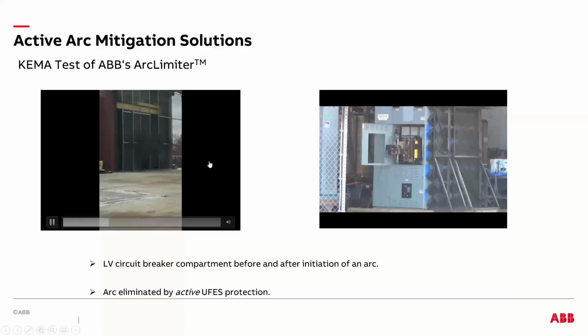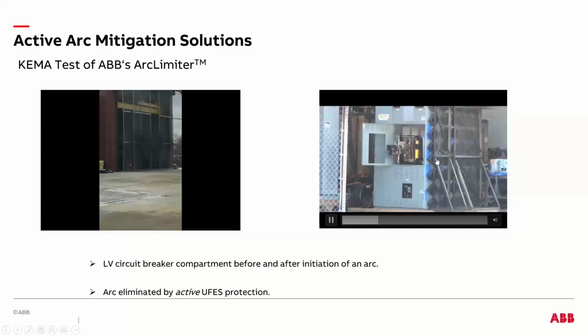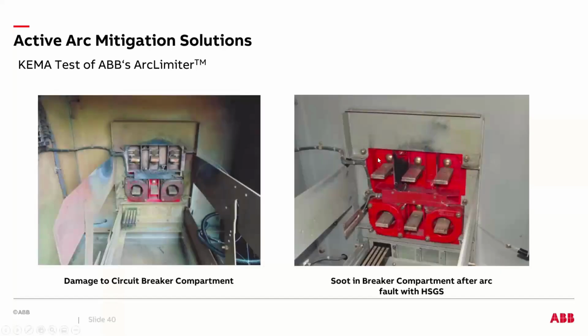And the video on the left, we did a test by using a conventional relay where the equipment just blew up, right? It's becoming like a ball of fire. Whereas on the right side, as you can see here, in less than 4 milliseconds, all you see is a little bit of soot coming out of the equipment, and that's what we see in the pictures, right? On the right side, we have a little bit of soot in your breaker compartment that you can clean up, and as you can see, very minimal to no damage within your equipment, where you can put it back in service much faster compared to the significant damage it caused in the first picture, where you may have to completely replace this particular breaker section, right?